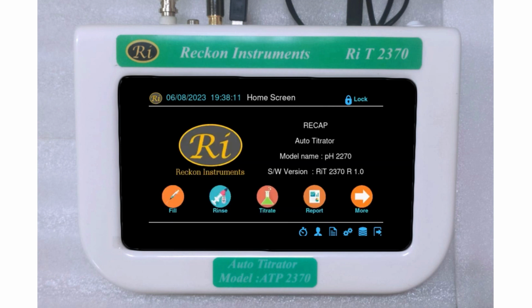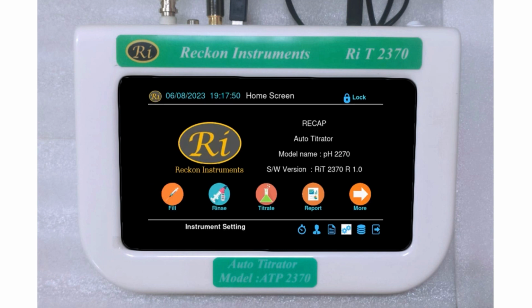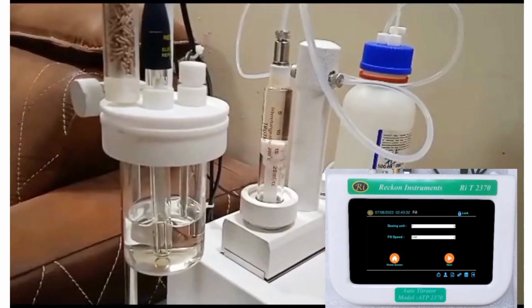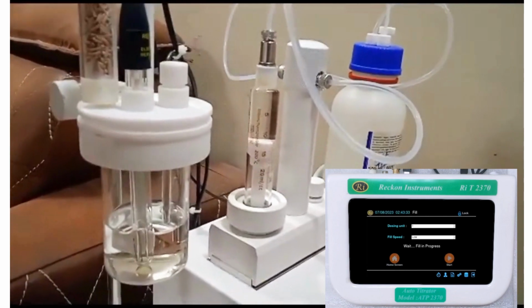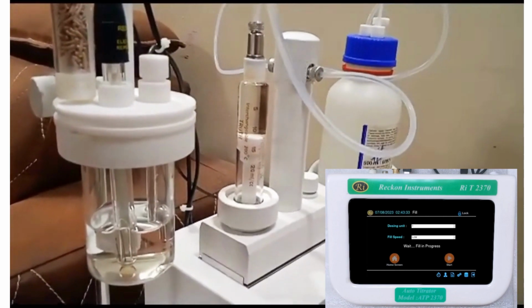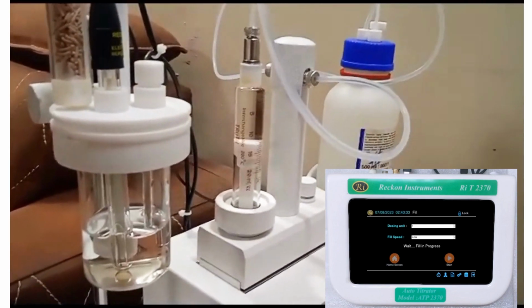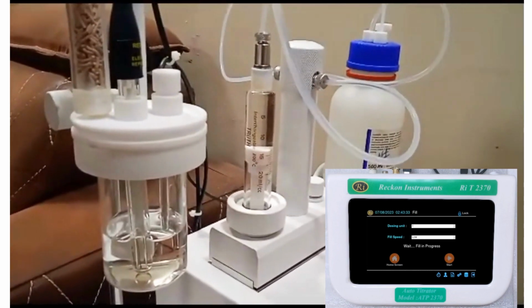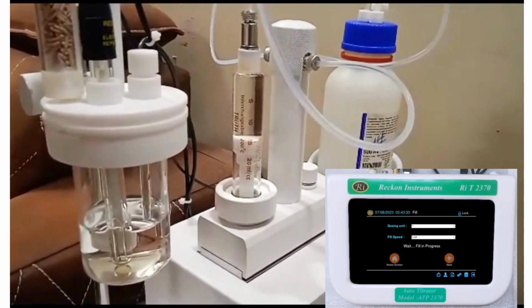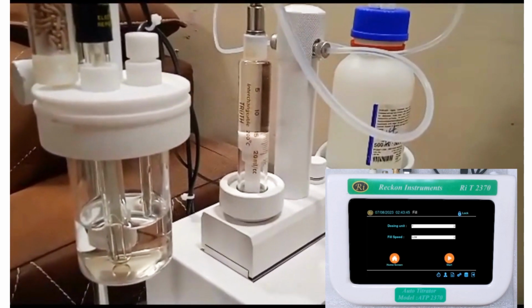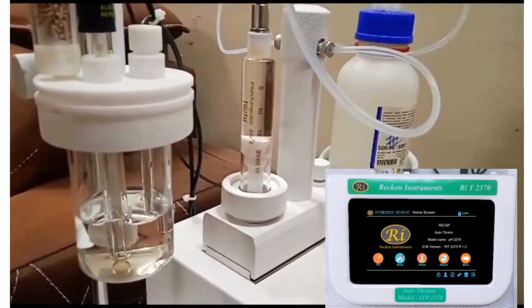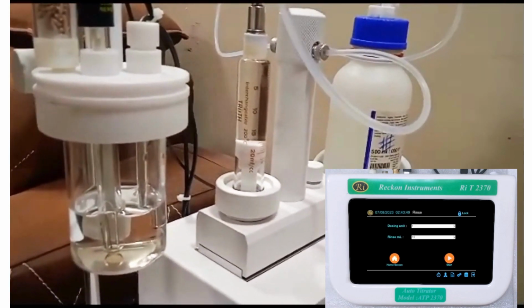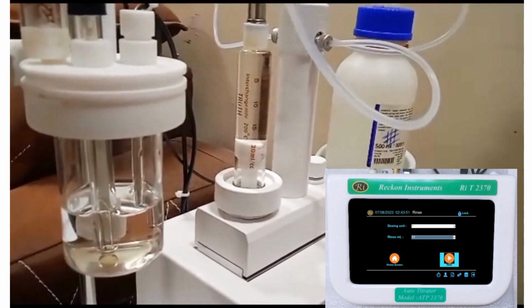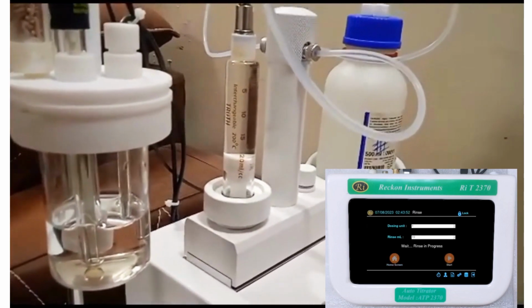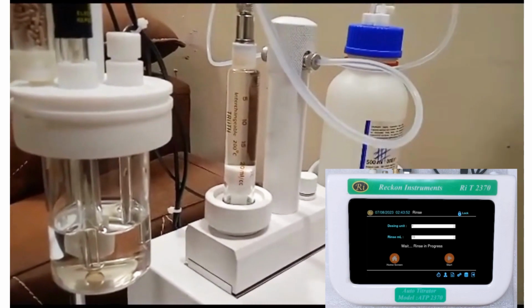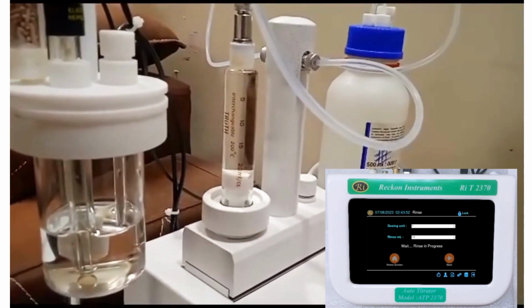Now to perform the titration, fix the interchangeable burette to the dosing assembly. Bring the piston and valve to their initial position and wait till the fill button is disabled. To rinse the burette, press the rinse key. Select the rinse volume and press the start key. Rinse operation will be started. It is used to avoid contamination.